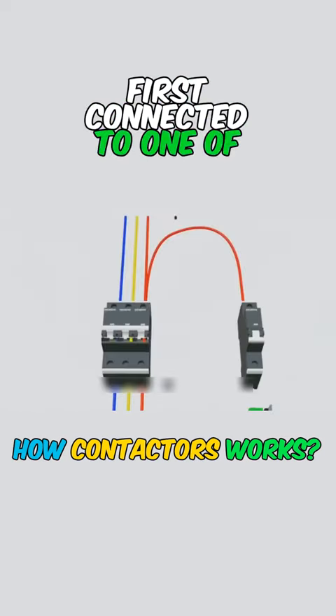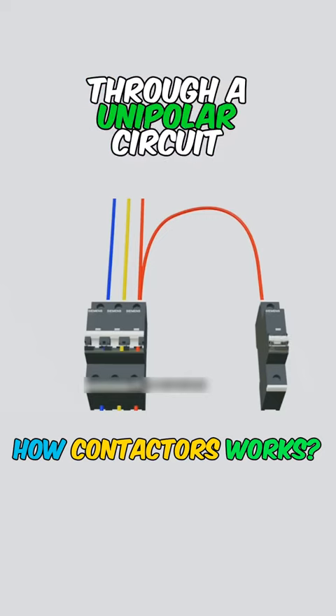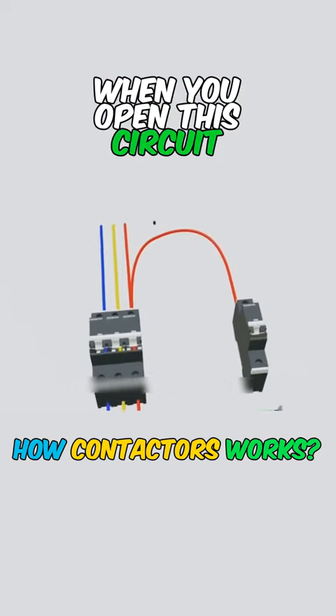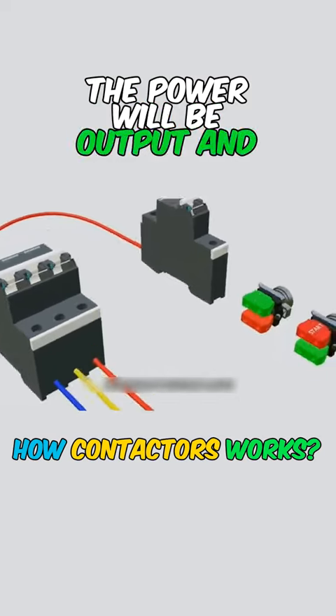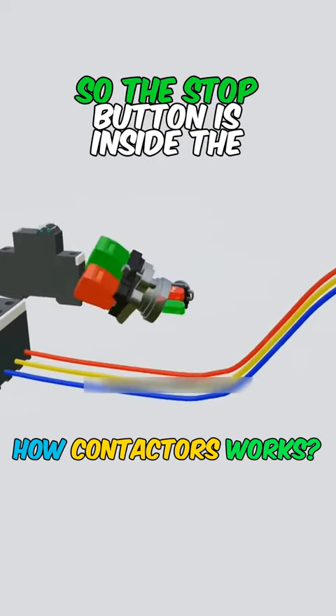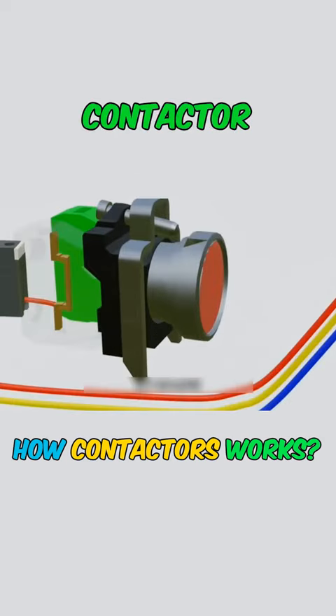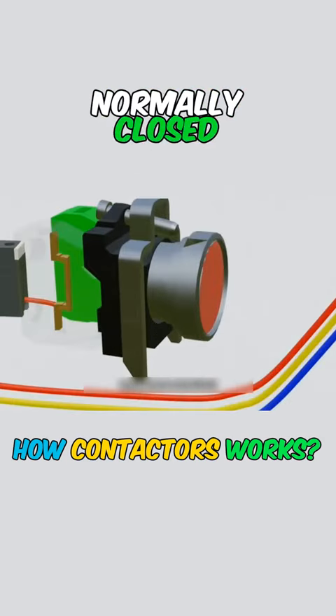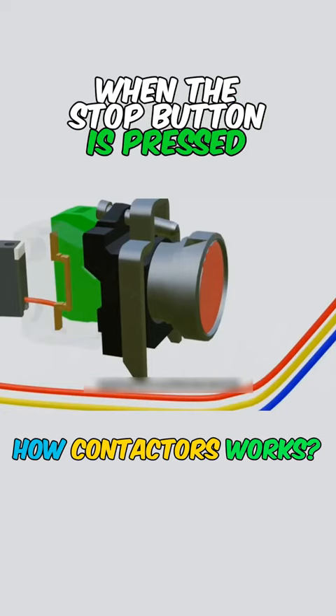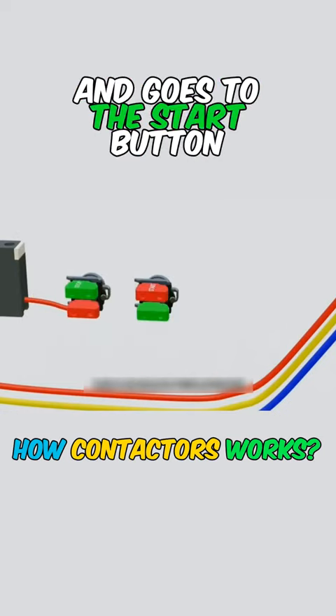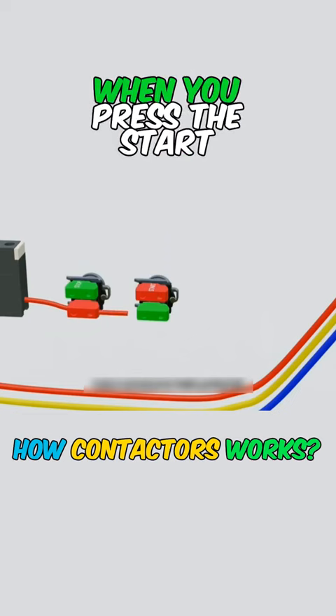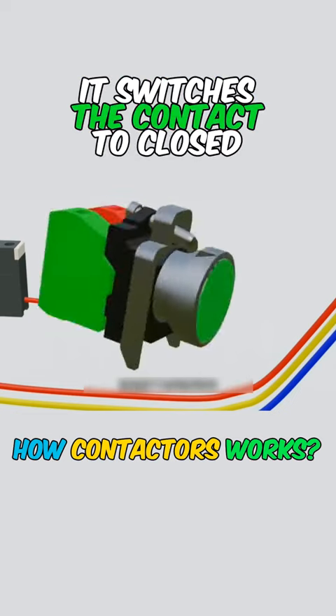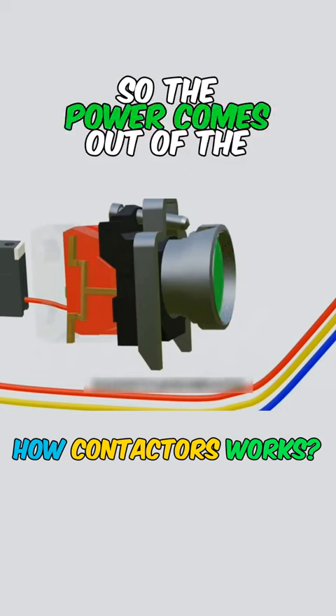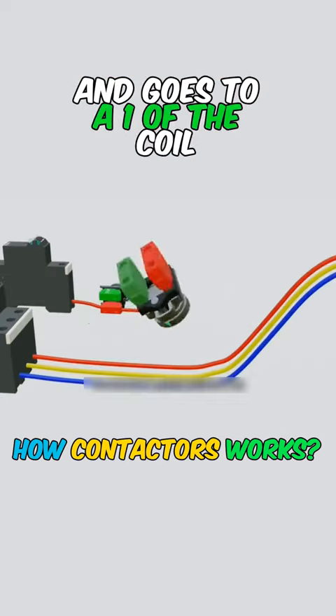First, connect it to one of the phases through a unipolar circuit breaker. When you open this circuit breaker, the power will be output and go through the stop button, so the stop button is inside the contactor. It has a long arm that is normally closed. When the stop button is pressed, the power is cut off from there and goes to the start button, which is normally open. When you press the start button, it switches the contact to closed, so the power comes out of the start button and goes to A1 of the coil contact.